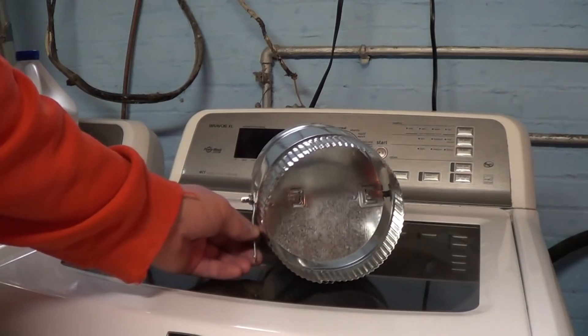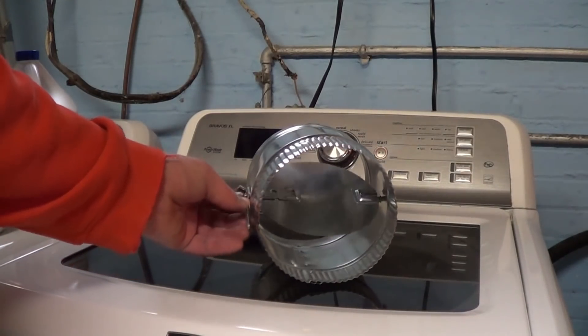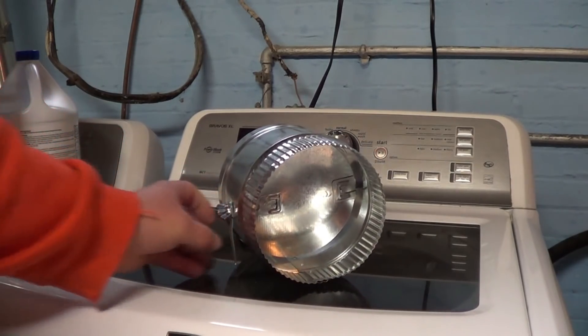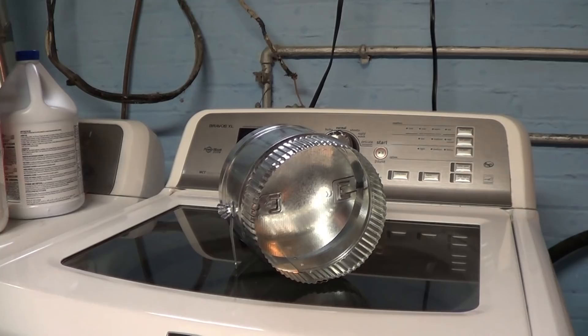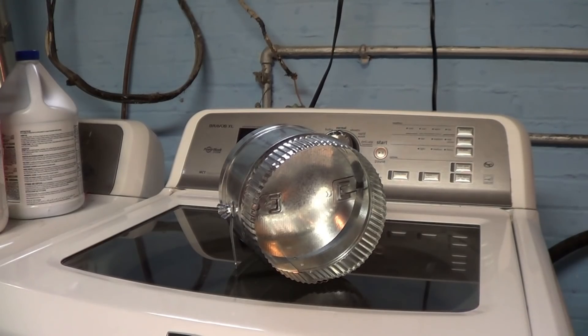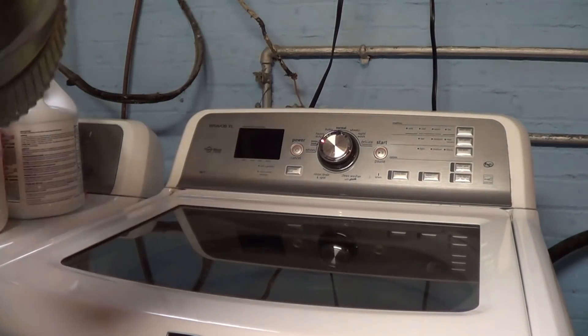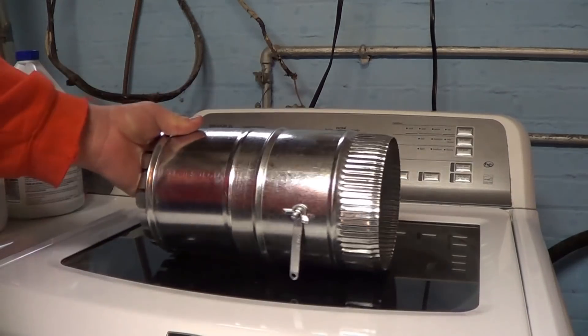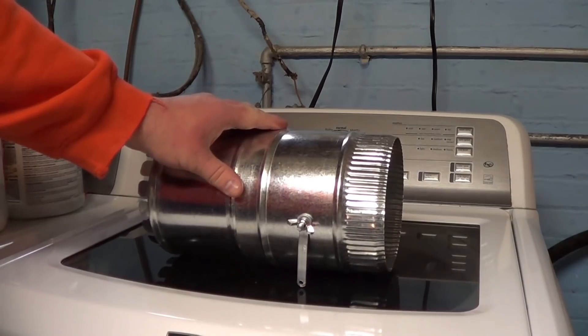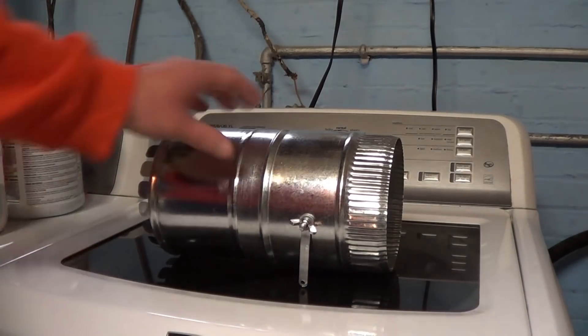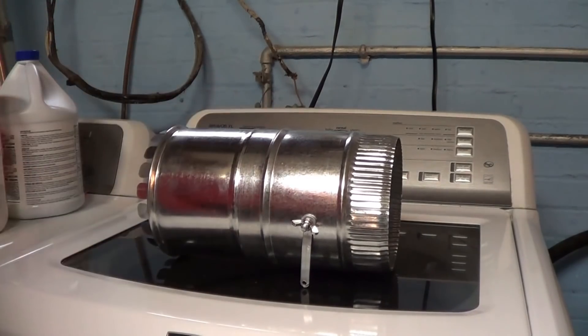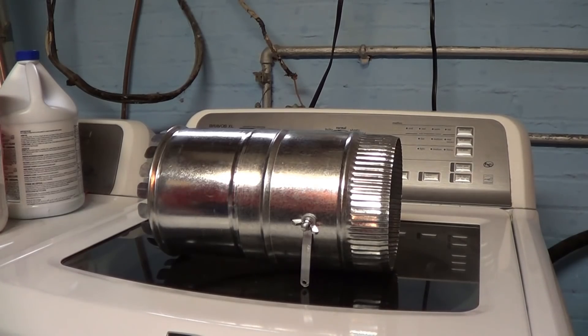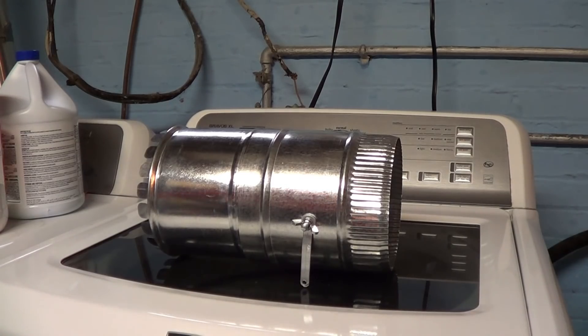I ended up getting one of these. This is a balancing damper. There's a little handle on the outside of it, and when you turn that handle, it operates a damper within this stubby piece of pipe. That allows you, at least in theory, to balance your heating and air conditioning system so that all your rooms are at equal temperatures. Of course, I have never been in a house where such is actually the case. These two pieces will end up going together. I'll use some self-tapping sheet metal screws or zip-ins to ensure these two don't blow apart, and then I may actually seal it for air leaks with some metalized furnace tape. I'm sure I'm going to be caned in the comments for every unprofessional aspect you see in this job. But oh well, you've got to start somewhere.